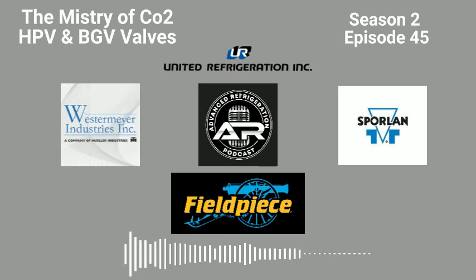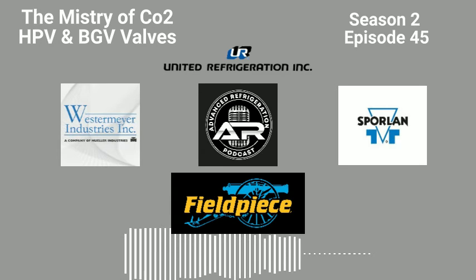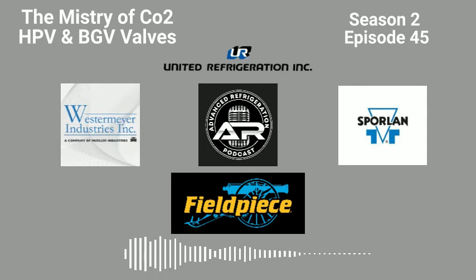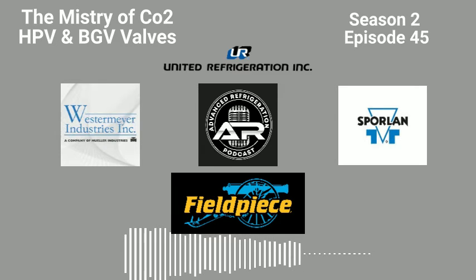100% correct. So when it's hot out, transcritical racks are extremely inefficient. I mean, you're running a lot of horsepower to pull that vapor off there. We have a couple racks over here where it's like 2 compressors are just dedicated to flash tank load almost. And that's a lot of horsepower. But then when wintertime hits and we're running drop leg temps of like 28 degrees, just frosty drop leg temps, like EnviroGuard style, and we're running super low head pressure and really efficient liquid, I mean, we're barely pulling any vapor off the top there. And this thing's just running like a top hat.